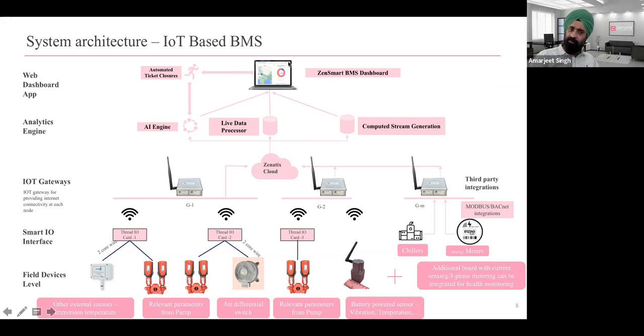Those controls are not only managed in the cloud. At every layer of this IoT architecture, the systems are now smarter. The local PID logic actually runs on the IO card itself at the lowest possible layer, meaning that even if the IO card gets disconnected from the gateway, it keeps doing its own operation.